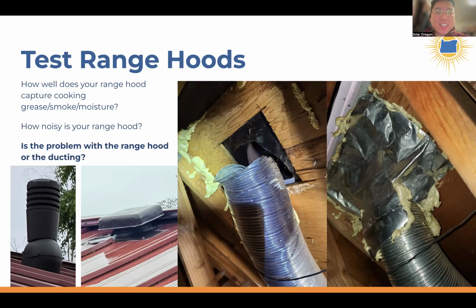Wrong pipe, wrong termination. Everything's wrong with this range hood, and it's no wonder this range hood is very noisy and didn't move any air. And so the solution to this was actually to not use the vent termination on the right-hand side of this photo, which is not even the correct type of termination for a range hood, and then to cut a hole in the roof to install a correct termination for a range hood, and then keep that original roof vent for its intended purpose, which is to exhaust hot air out of the roof.